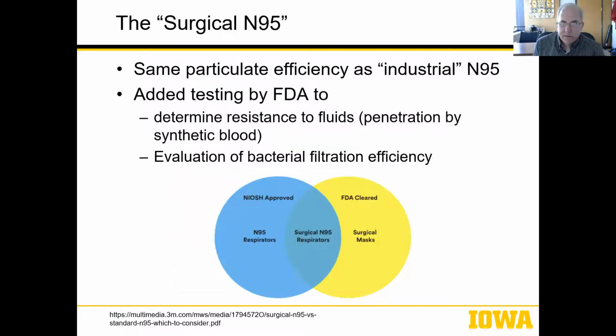So again, just getting into the surgical N95 a little bit more, it was designed off of the N95 as I've just described it, with additional criteria established by the FDA because of the hazards within a hospital setting, of which you could be splattered by fluids of all different types as one thing. So it has to pass a test for resistance to fluids. And they use synthetic blood for that testing. It also has to pass a certain bacterial filtration efficiency.